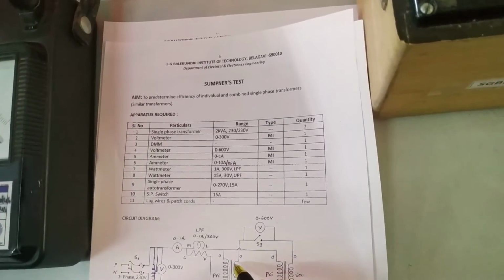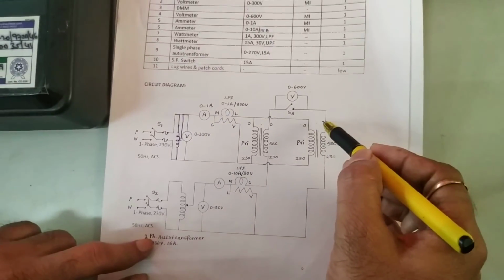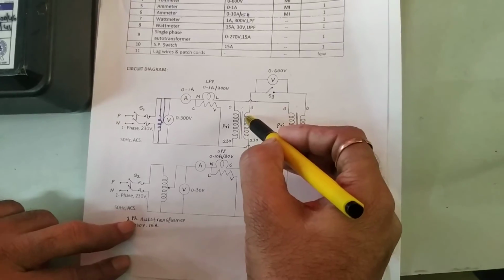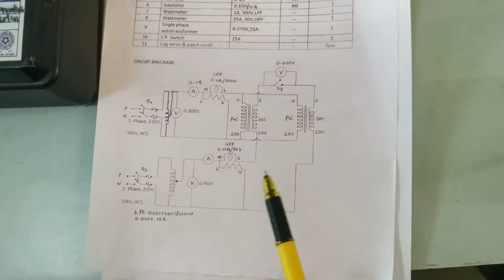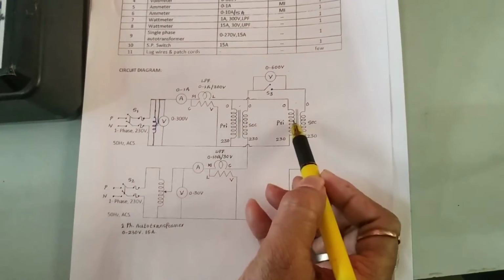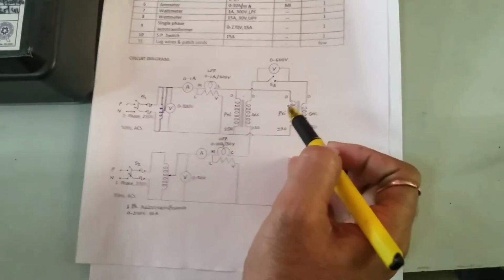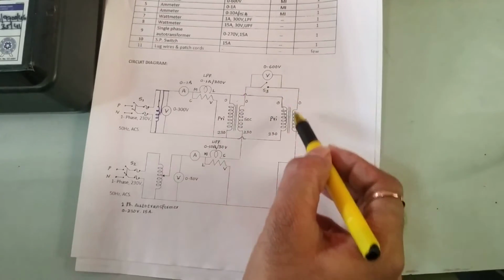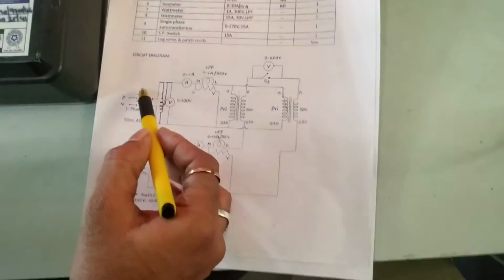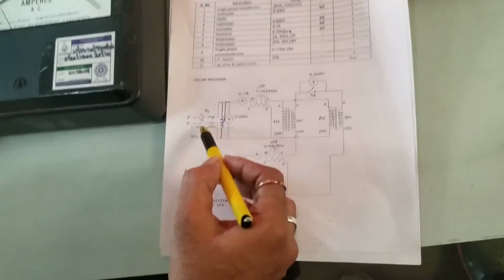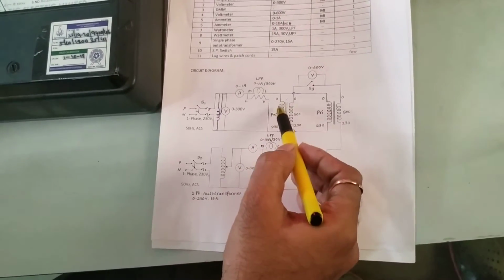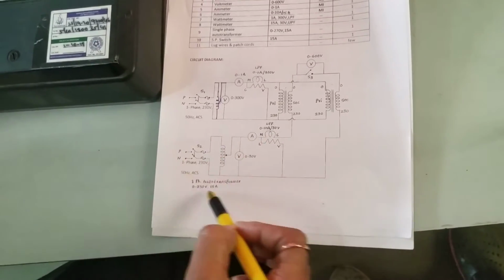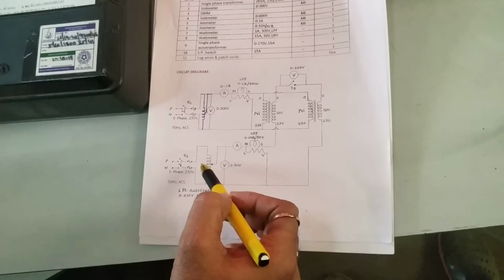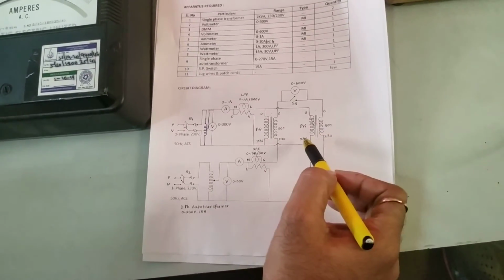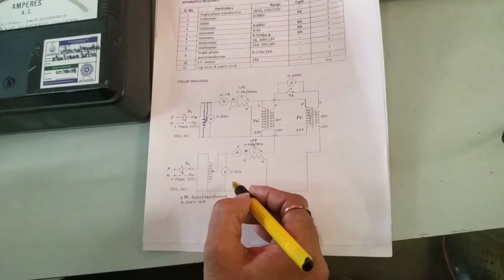The main intention is to determine the efficiency of the individual transformers, transformer 1 and transformer 2 separately, and we can also calculate the efficiency of the combined transformers. As you can see from this circuit diagram, the primaries of both the transformers are connected in parallel, and the secondaries of both the transformers are connected in series via the switch, right? First we need to apply the voltage across the primary of both, that is we are applying 230 volt, which is the rated voltage of the transformer. After that, with the help of another source and a single phase auto transformer, we need to apply a reduced amount of voltage to the secondary of the transformer to get the rated current in the ammeter, that is 8.69 ampere.